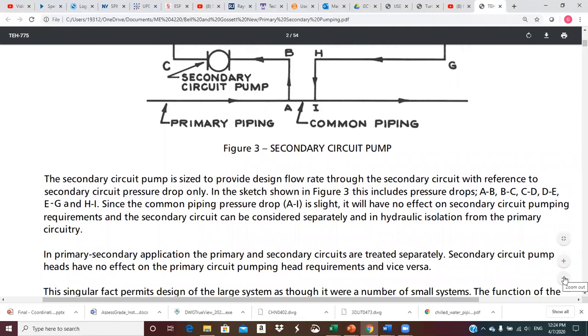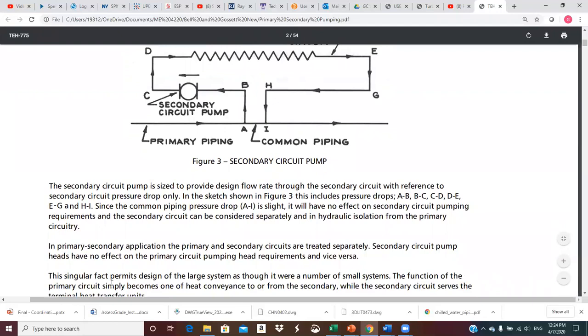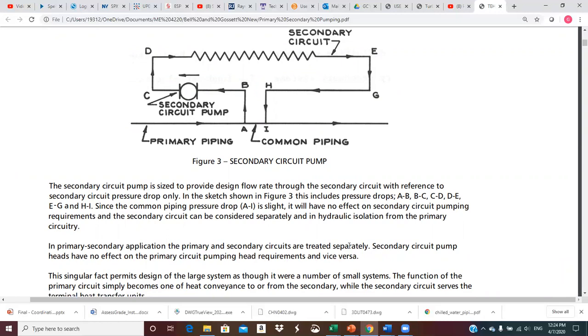In primary-secondary application, the primary and secondary circuits are treated separately. That's one of the big positive benefits — you could have one group of engineers working on your primary piping and a separate group designing all of your secondary circuits, and they don't really need each other very much. Secondary circuit pump heads have no effect on the primary circuit pumping head requirements, and vice versa.